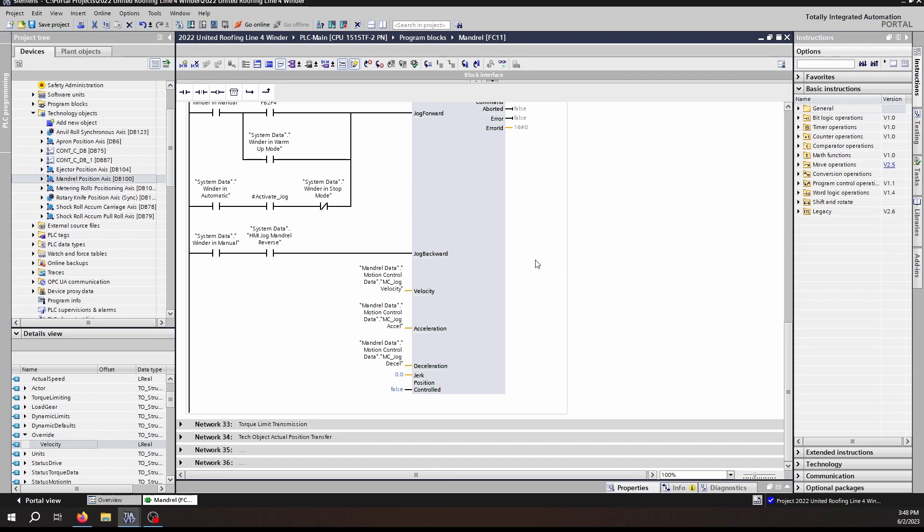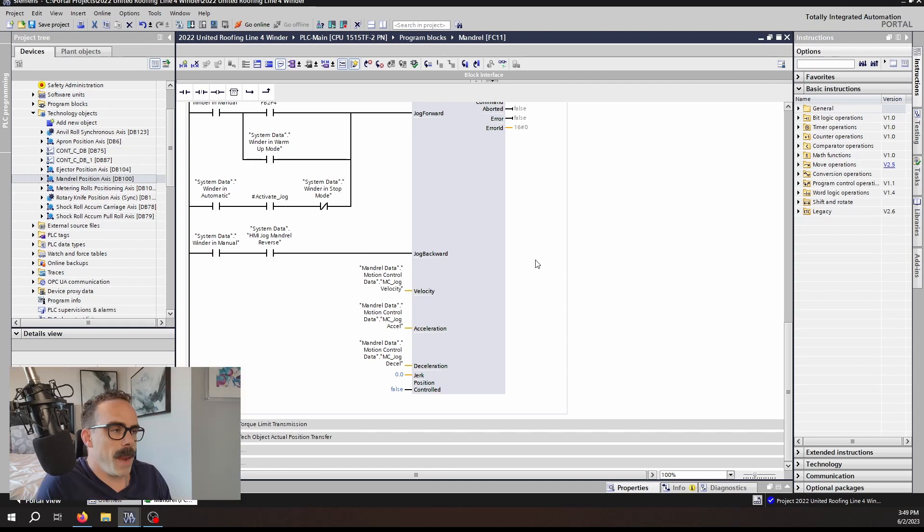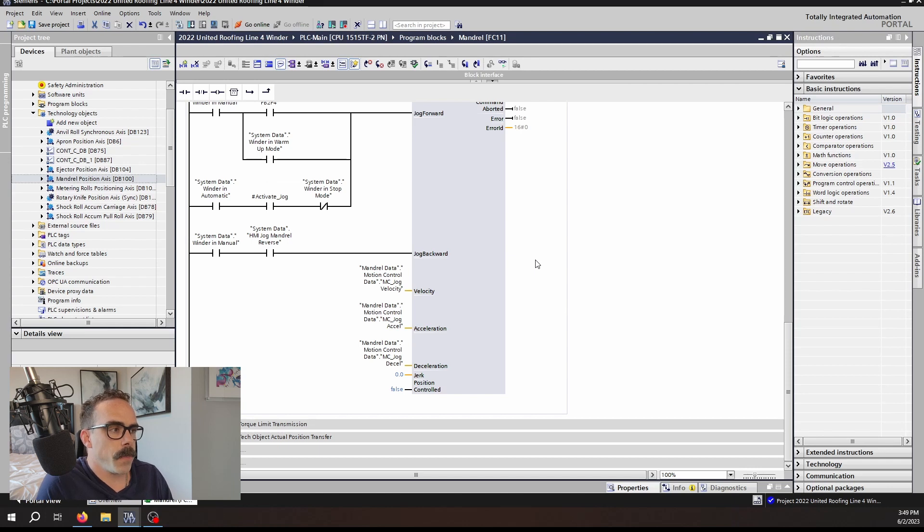We talked about the position controlled in the MC Velocity and it works the same way. Essentially all movements of a technology object have the ability to be verifying the position in addition to the speed. What that means is if you are doing a position controlled jog, you are only controlling the velocity, but it is keeping track of the position to make sure that it is keeping up with that set point.